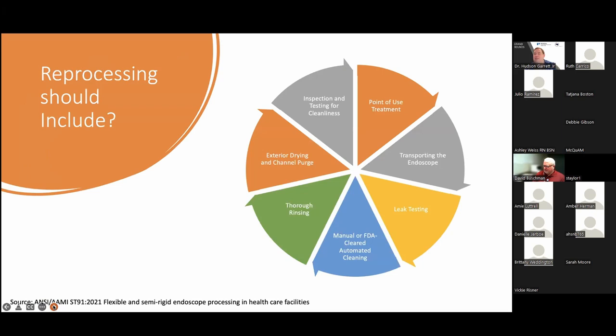Reprocessing itself can mean different things to different people, but part of this is to render the device as safe as possible for the next patient's use. Now that may be sterilization, where we're removing all microbial life. It may be high-level disinfection, or it may be reprocessing like a blood pressure cuff, where we use a low or intermediate level disinfectant.